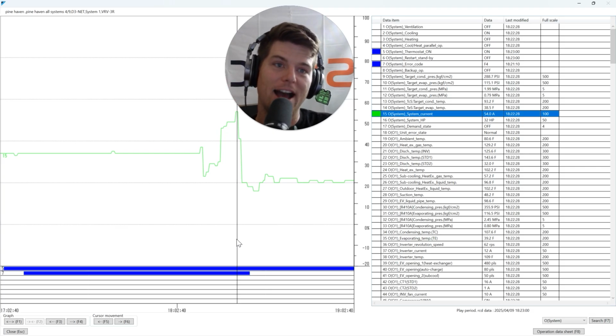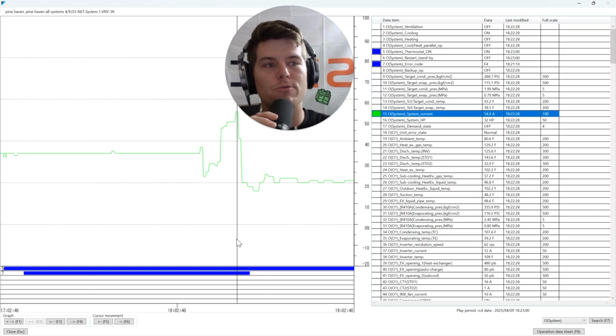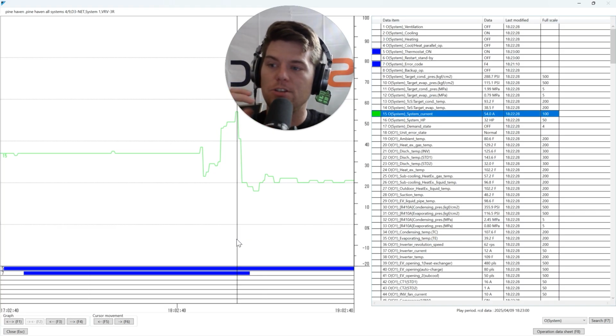This is probably the highest amount of demand. Remember, amps correlate to what? High compressor speeds. Why would we have high compressor speeds? Well, you'd have high compressor speeds during a high amount of load or demand on the system. And so if you're trying to find the root cause of a problem, when I teach technicians and when we talk about VRF as a whole, it's important to understand that you do have to run these systems to stress them out to find the problem sometimes.